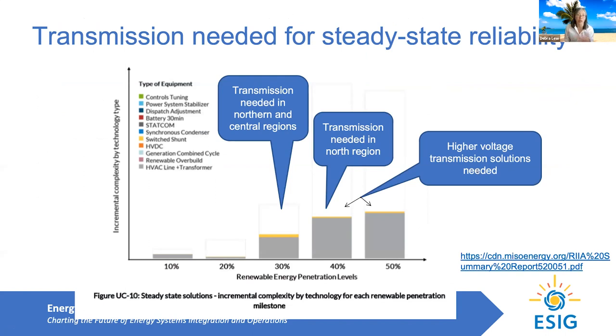They also find that transmission is needed for steady state reliability. So here, they're running a load flow model. They're looking for thermal overloads. They're looking for voltage being within limits. They're looking at normal operation. They're doing an N-1 contingency analysis. And they find that starting around 30%, you need to start adding more transmission to manage your thermal overloads and manage your voltage within limits. As you get to the higher penetration levels, you need higher voltage transmission solutions, so you need higher transfer capacity.